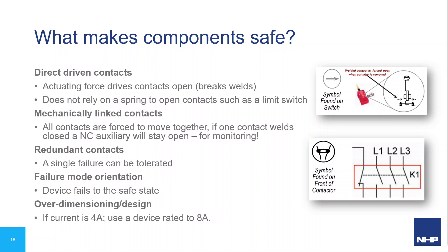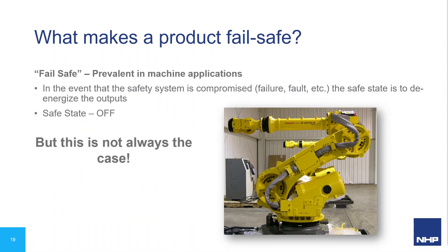Safety devices are designed so that when they fail, they also fail to a safe state — this is called failure mode orientation. Over-dimensioning is another feature: if you're switching 4 amps, you select a component rated for 8 amps to further reduce risk of failure. In machine safety applications, the typical fail-safe state is to remove power from all outputs. However, the failure mode orientation always needs careful consideration to make sure it's suitable for the risk being reduced — you can't have a device turn off and produce an even more hazardous situation.